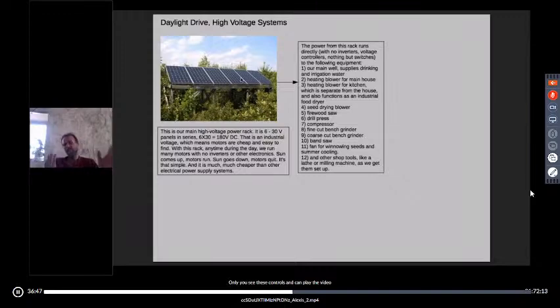There's no electronics, no computers, not a single integrated circuit anywhere between these PV panels. Each panel has a diode in it, a very simple electronic device the manufacturer put in just to make sure the panels don't draw electricity back out of your batteries at night. Then there's the DC brush motors, that technology hasn't changed since the 1800s. So there's not a single transistor, resistor, or integrated circuit, no electronics whatsoever, aside from those diodes, which makes it a very simple, durable, flexible system. Sun comes up, motors run; sun goes down, motors quit.